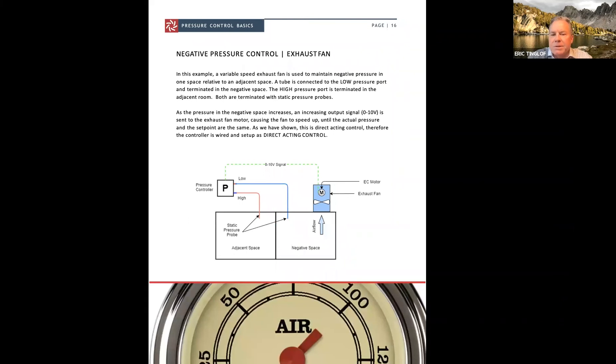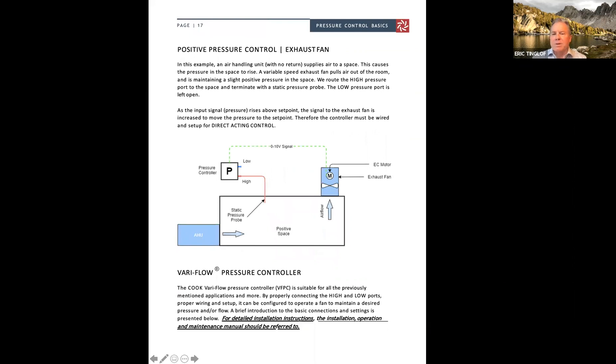And then negative pressure is exactly the opposite where you have a fan on the negative space, trying to maintain negative versus the adjacent space. You have the low pressure, the high pressure hooked up as shown. And as this negative space, as the pressure is going higher and you want it to be lower, obviously, then again, the pressure is going up, so you'll send a signal back to the motor to speed up. Positive pressure, very similar. Maybe you have an air handler or a fan moving that air into this space, sending a signal back to the motor, again, direct acting control.